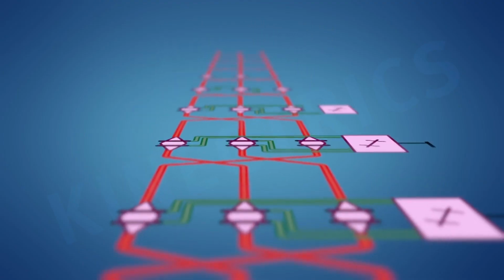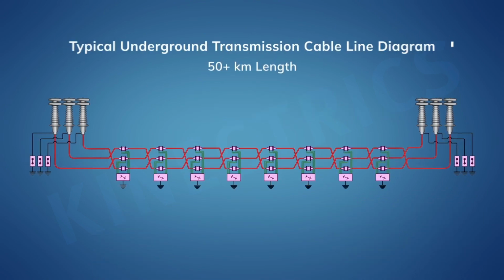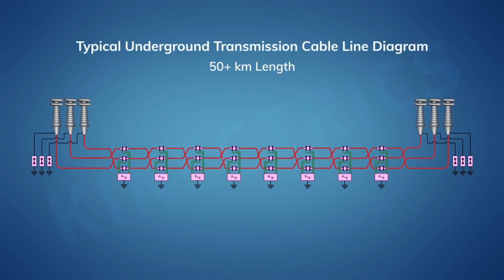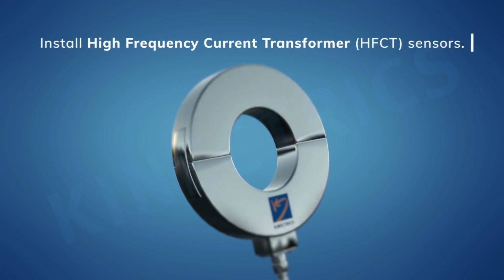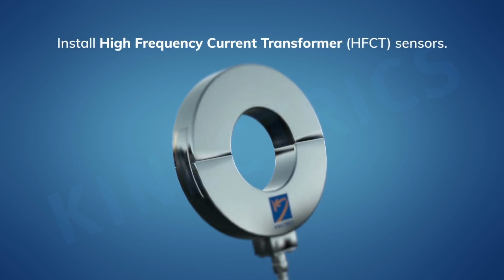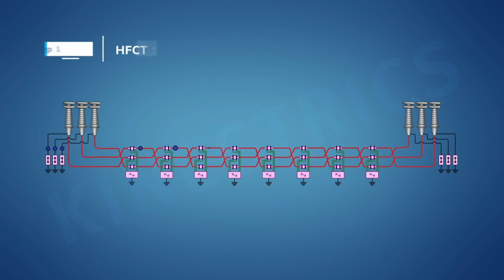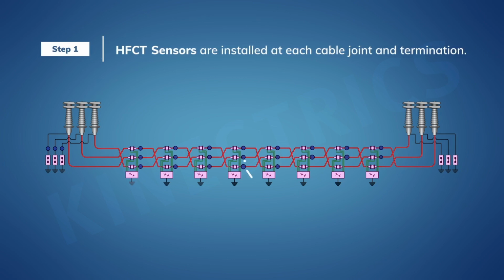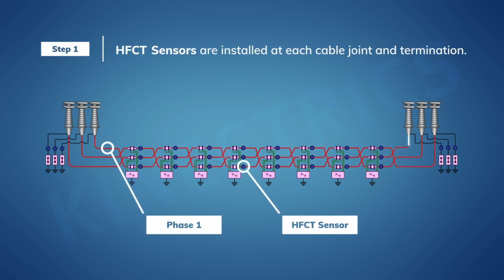This shows the setup for a long cable circuit. This is a cross-bonded circuit, so it has a number of joints which are bonded in link boxes. Well, we're going to apply partial discharge sensors to all those link boxes and all those bonding leads. But we're going to test one phase at a time. So this means we're going to have partial discharge sensors on the phase we're testing, and then after one phase test, we're going to switch everything over onto the next phase and do that phase and so on for the third phase. Well, we have a solution for that.